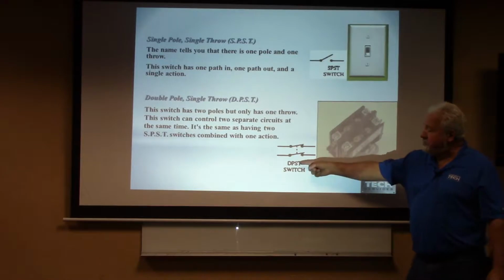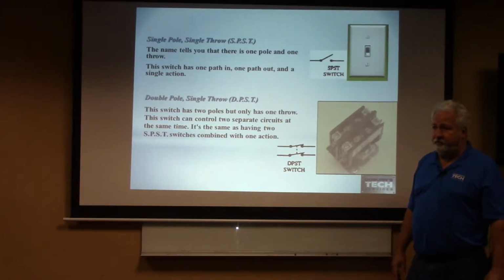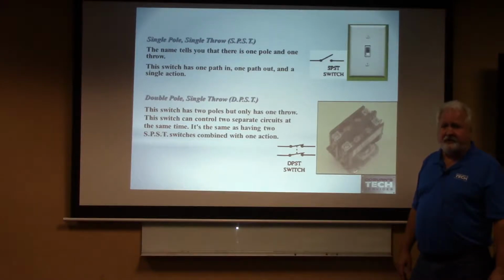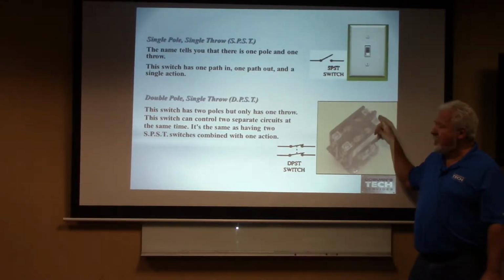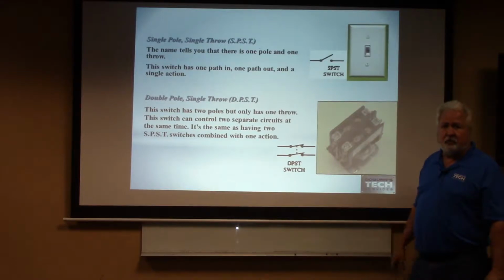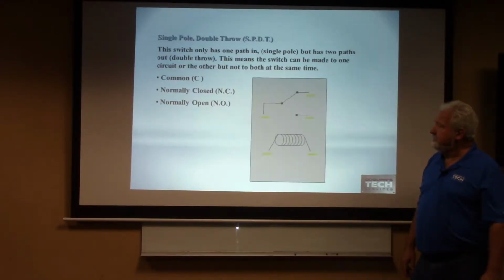So that would be a double pole, single throw switch. Everybody good with that? Double pole. Could I have a triple pole, single throw switch? 3-phase contactor. Could I have a single pole, single throw contactor? Yes, you've seen those. Sometimes they call those 1.5 poles, right? It's two different poles, but they'll just put a wire right across there. Good, we'll call it a 1.5 pole sometimes. Good. You're understanding that.